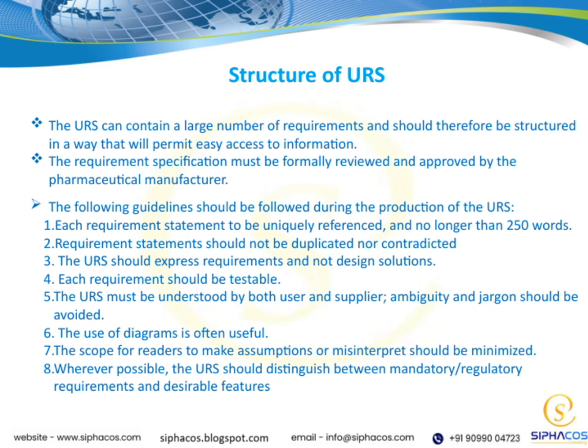Third, remember that the URS should focus on expressing the requirements, not the solutions or designs. It's about what is needed, not how to build it. Fourth, each requirement must be testable, meaning you should be able to verify if it has been met. Fifth, the language used should be understandable by both the user and the supplier. Avoid ambiguity and jargon that could cause misunderstandings.